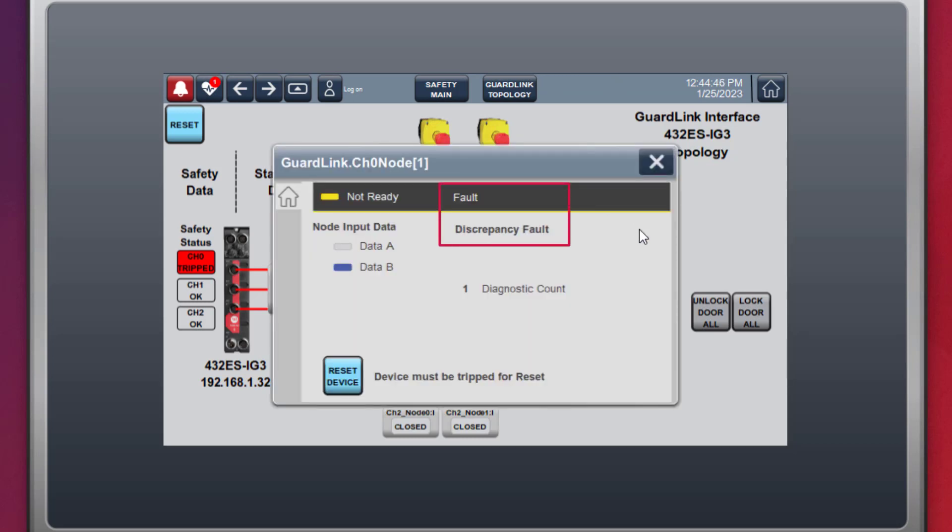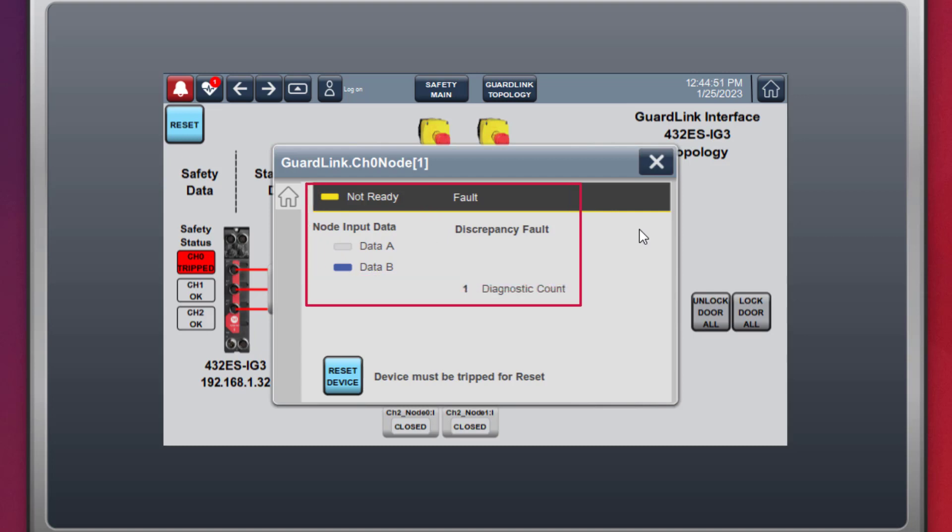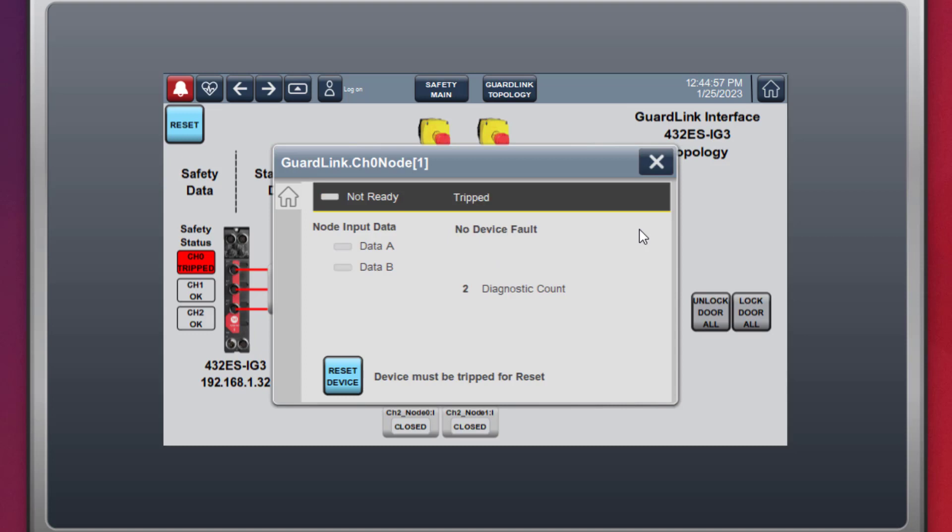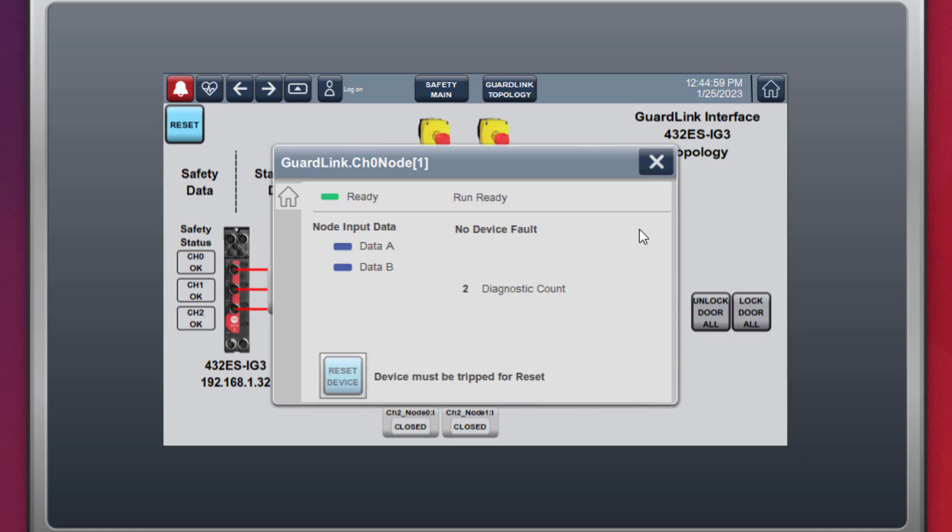the faceplate displays the discrepancy fault, the loss of data channel A, and displays the increment to the diagnostic count for the node. To recover from the fault, the wire is replaced, shown by data A coming back on. Following the prompt, the device is cycled by pushing the e-stop push button in and out. The node is now run ready.